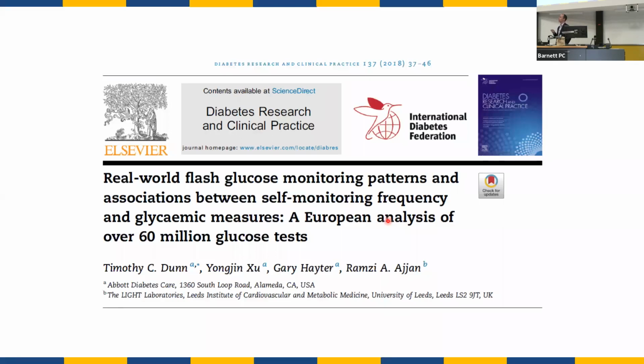And the same at the extremes. And in fact, some of the companies, the Dexcom data I showed earlier, they've been fairly honest. They included data up to the maximum of the device they were using to reference it against, which was into the 30s. But some of the devices, to get their accuracy, they only report within a narrow range. So they remove all blood glucose values above 30, say. They remove all blood glucose levels below 2. And then they give a reported accuracy for that range. But of course, when you're outside of that range, they may be far more inaccurate than they report. In fact, some of them as much as 20% inaccurate. When they're in target, they report to 10, but then they go out to about 20%. So there's quite a range.